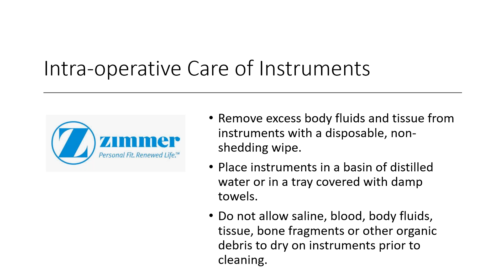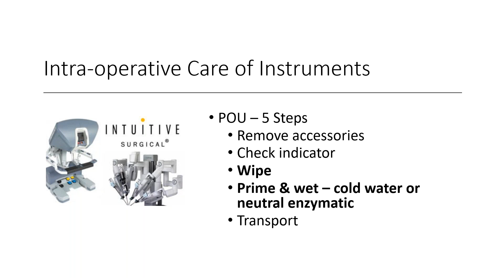Da Vinci. Most of us are pretty familiar with Da Vinci nowadays as robotic surgeries increase. Well, they have a whole section of their cleaning and reprocessing dedicated to point of use. In that, they say those instruments need to be wiped down. They need to be primed and wet with cold water or neutral enzymatic. This is an interesting one that I would ask administrators and quality control managers, people who are really auditing the process, to get in the OR for and see if they're actually priming those flush ports on the Da Vinci instruments, because there's no way to get inside of a Da Vinci instrument and see if they're actually clean.